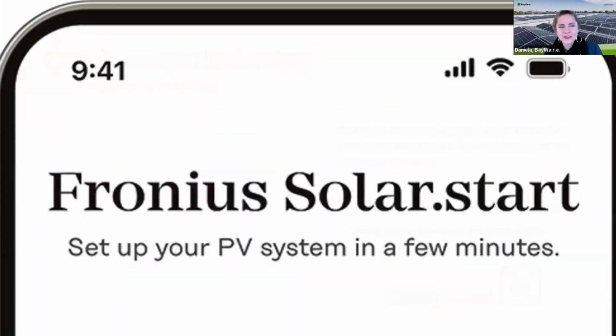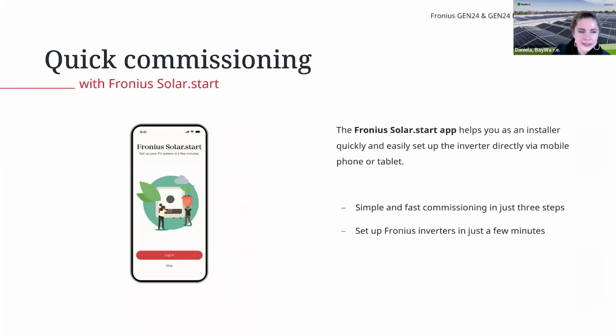Quick question here. When you install a Fronius Gen24, there's no torque, correct? That is correct. To get into the inverter, there are 180-degree locking screws. And the terminal blocks themselves are actually removable Wago terminals. So you just remove them, open up the spring clamp, and make sure the wire is stripped properly. Once you land it, close the spring clamp and click it back in. It makes it really simple and easy to install, much better than our previous generations. Thank you.